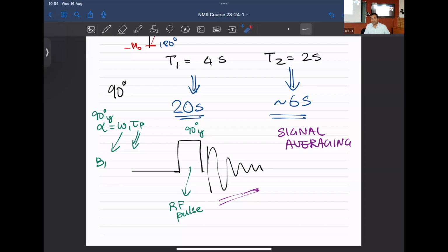Was that a question? How many iterations do you normally use? That depends on the signal to noise. Those are very good questions. Remember, I defined something called signal to noise ratio should be minimum 3:1. If you have less sample, you may not be able to get 3:1. So you go on until you get 3:1, for instance. Generally, people like 10:1. 3:1 is still borderline.